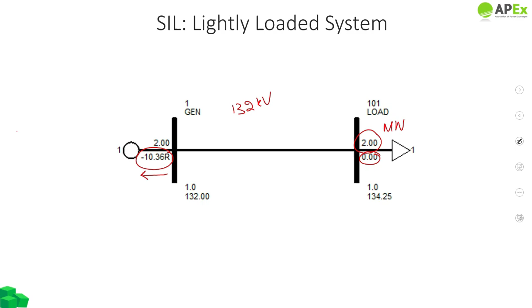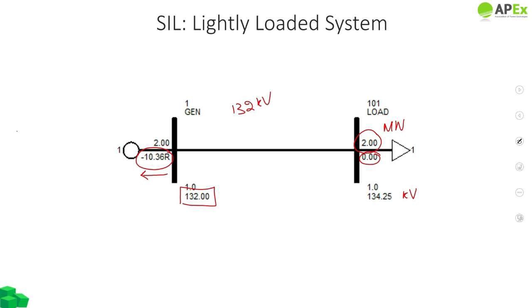What does this signify? This means that when the line is loaded below its surge impedance loading, the receiving end voltage increases, and this is because of a phenomenon called the Ferranti effect. So when the line is producing megavars, the voltage at the receiving end increases. This is a key point to remember moving forward. But in both of these cases, the common factor is that the sending end voltage and the receiving end voltage are not the same.